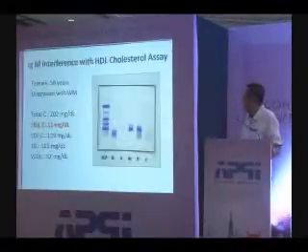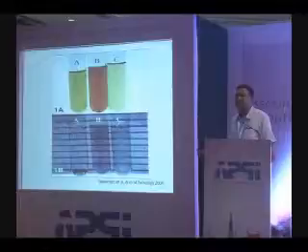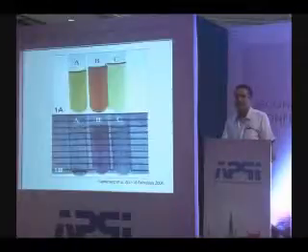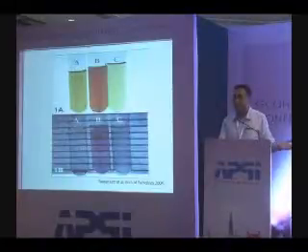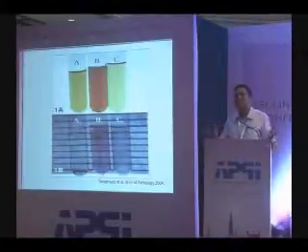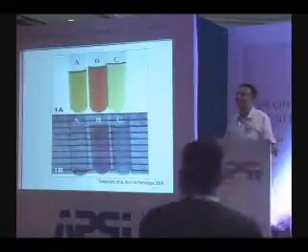What was the alternate method you used? In the case of the HDL one you are talking about, we found the interference on a Beckman-Coulter system and the Roche system gave the right result. In the bilirubin case, it was a very interesting case. I actually do not like to disclose the names of companies, but it was the same manufacturer. On one of its systems, there was interference. On the higher end model, there was no interference. It was because the same manufacturer has two different blanking principles for each different analyzer. So one was interfering, the other wasn't.